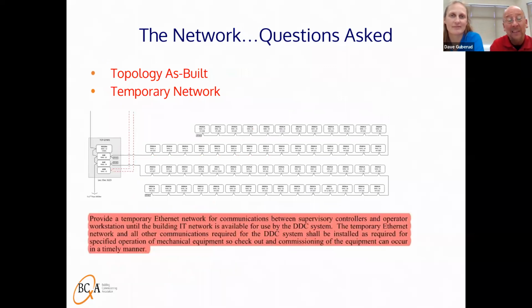is we like to see within the control specification the request to provide a temporary network between supervisory controllers, so that the control contractor can likely start early and get his system up and running before IT becomes available. Because sometimes we don't have that clean, secure, and tempered room, so the IT people aren't even going to be putting their switches in place. But a lot of times that infrastructure is already there. So a control contractor, purchasing from Amazon a few $5, $10, $15 switches or whatever, can actually use part of the infrastructure to create their own temporary network. It's not necessarily as expensive or drawn out a process as they like to make it seem sometimes. No, and we have to work hard, because they still do, to your point, Rachel, try to make excuses to wait. And we're out there pushing, saying, no, you can't wait. Right.